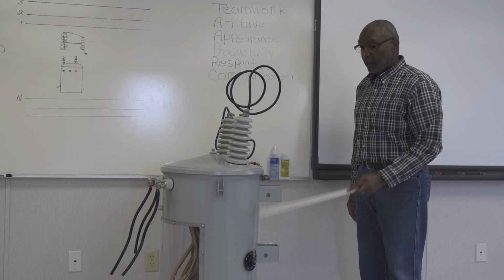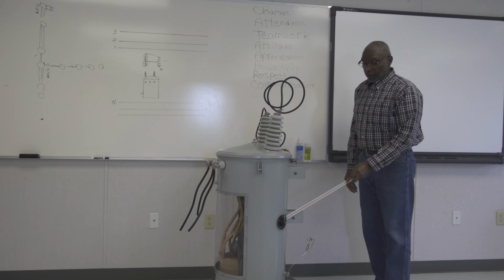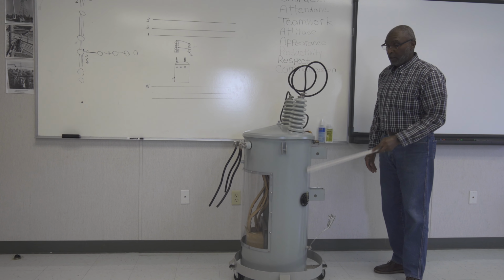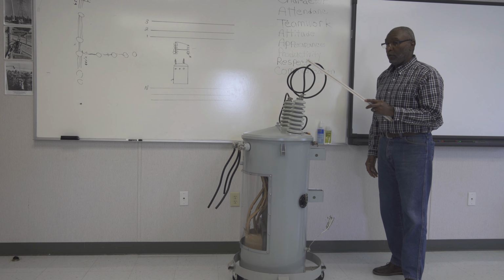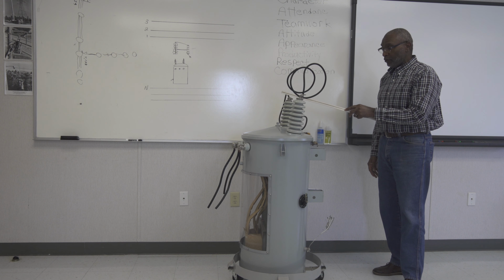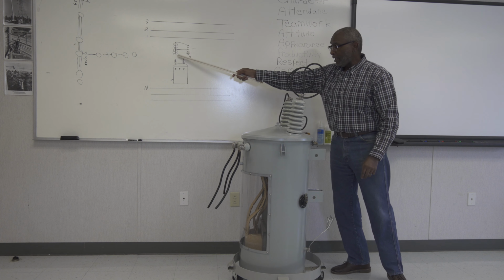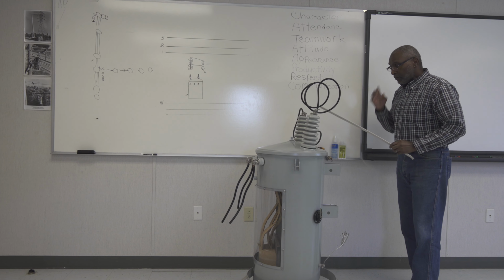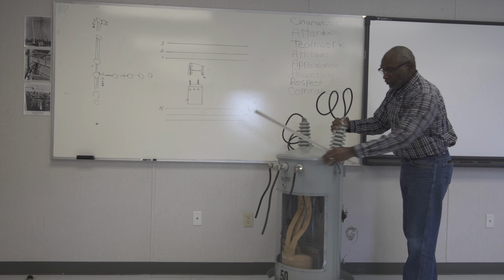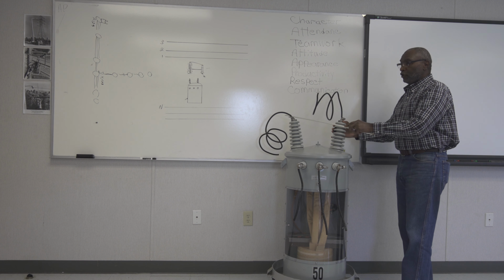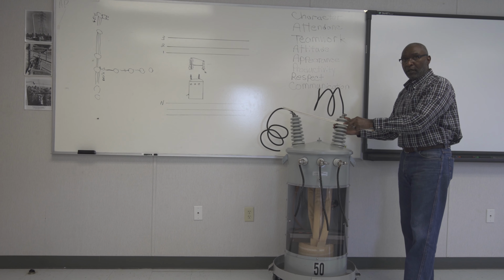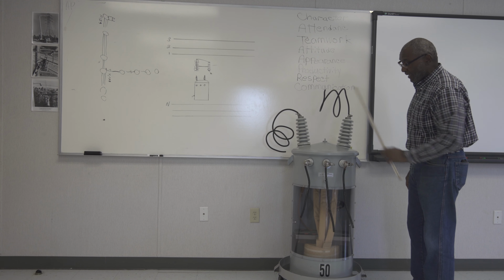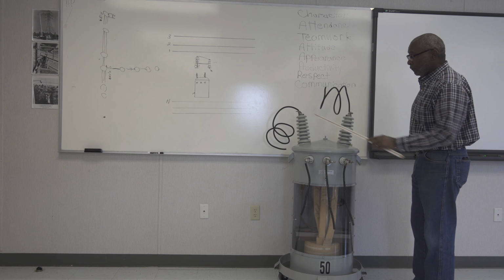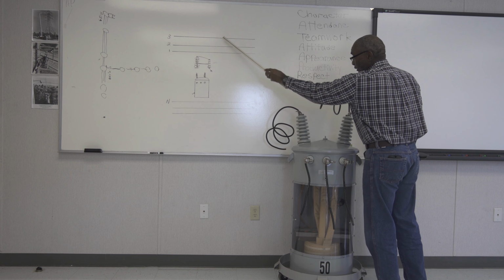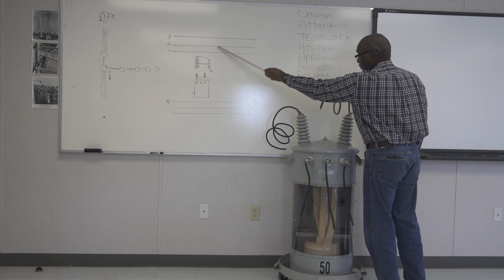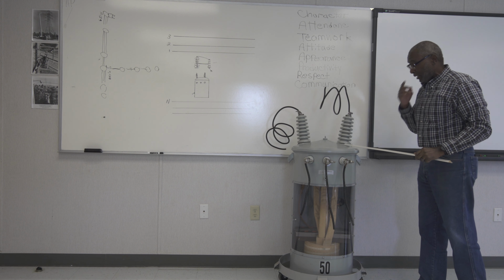What you have on this particular one, all of them are not like this, but this is a tap change to change it from your primary voltage. In other words, on your high side, on the one that's going to your primary here, on this tap change, you can change it from 7,200 volts to 14,4 on the primary side. You will still get the same readings here, even with the tap change on your primaries, and that's indicating 3 phases, phase 1, 2, and 3 on your primary on the drawing here.